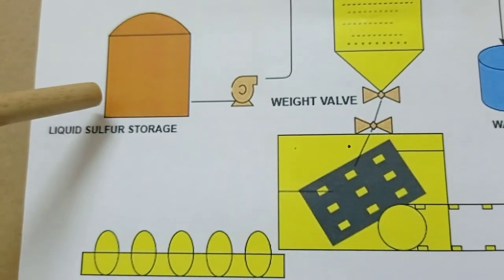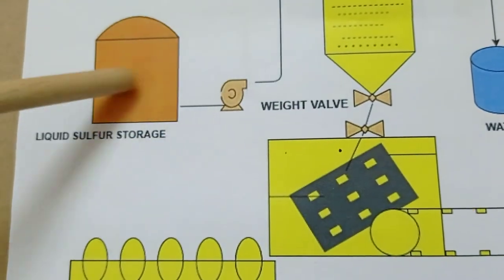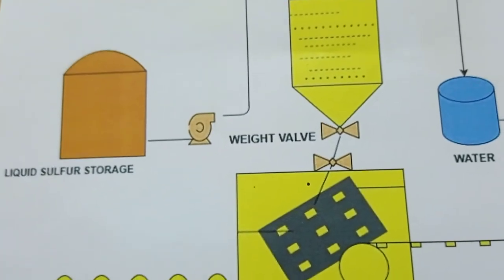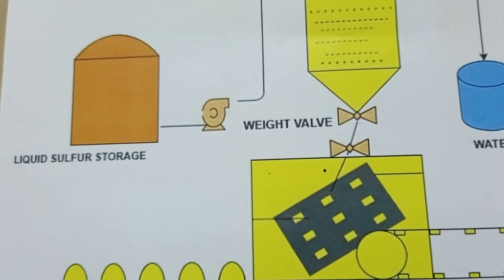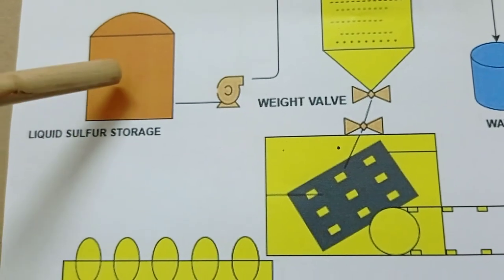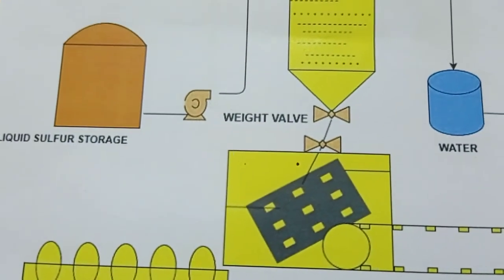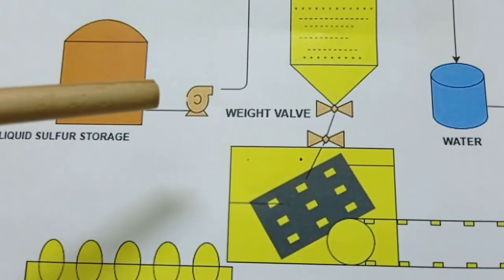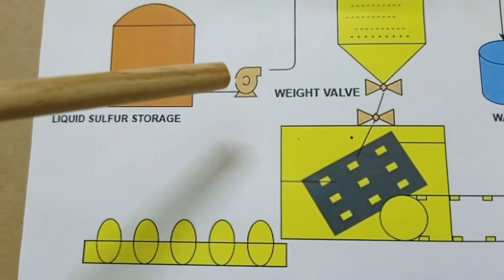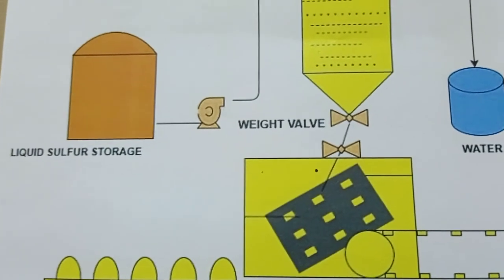To store liquid sulfur in the tank, we need a continuous supply of steam. If we don't supply steam, the lines will get choked and the tank will completely solidify — a very difficult handling situation. The cheapest way to maintain temperature is via steam coils jacketed inside the tank. All lines are steam-jacketed lines, and even the pump is steam-jacketed. We use a mono pump, ratchet pump, or vertical pump — special pumps designed for sulfur service.